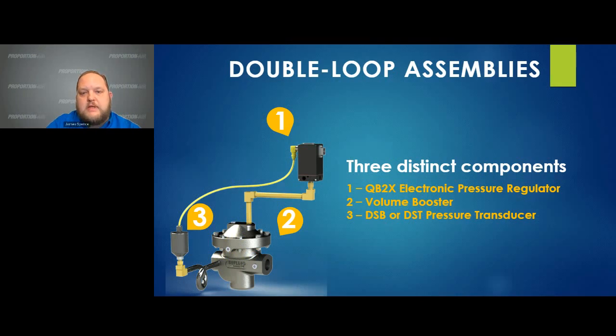One of our objectives today was to cover how to maintain accurate pressure in a high flow process. We've already explained how our QB3 has an integrated volume booster. The two-loop assembly with an external pressure transducer, like in the injection molding process we just showed, is another great way to accomplish pressure control in high flow processes. In this assembly, the QB2X unit pilots a volume booster, which you may know as a pilot-operated regulator or dome-loaded regulator, like pressure reducing or back pressure. The volume booster allows for additional flow to the application.